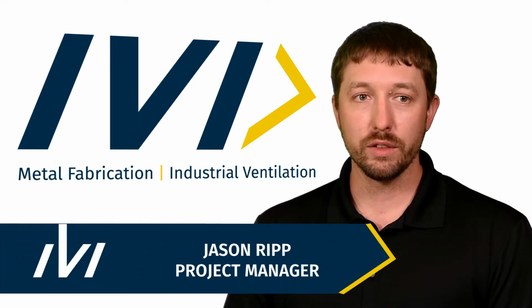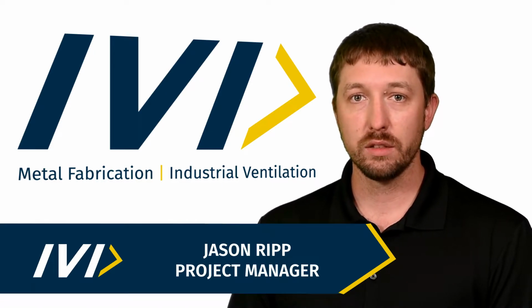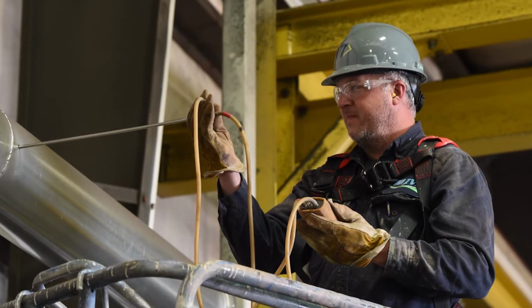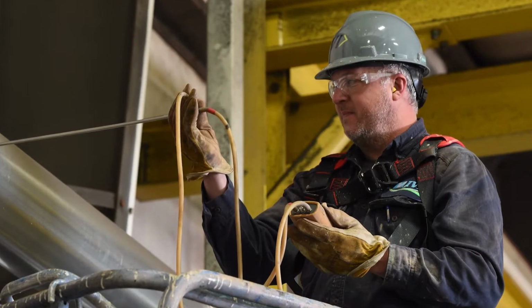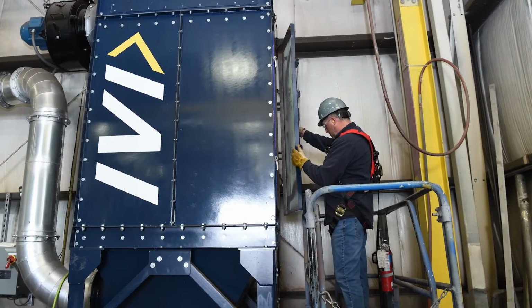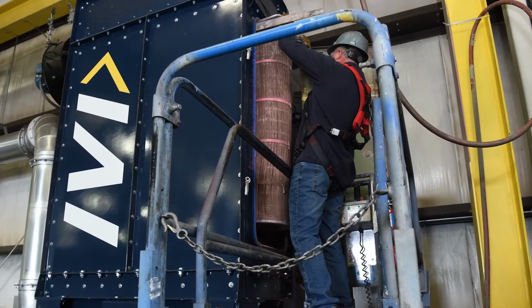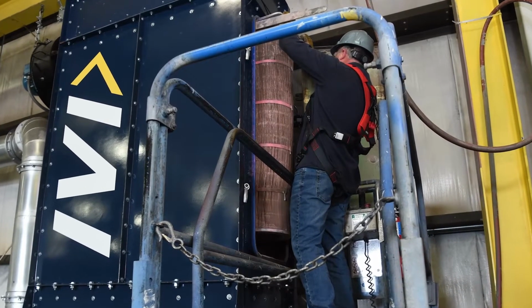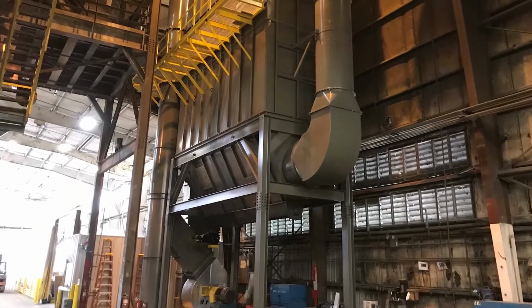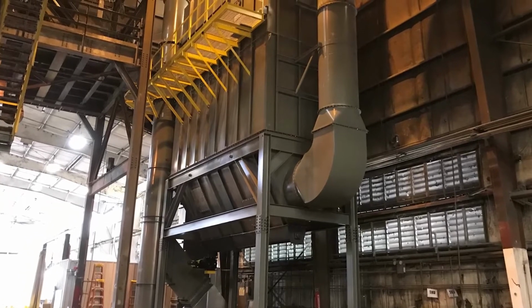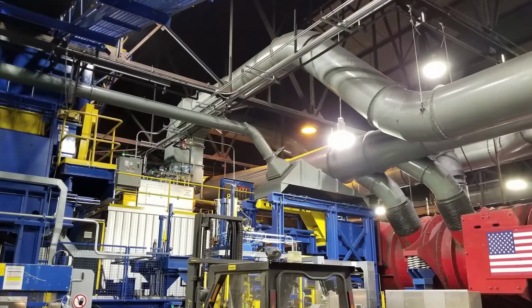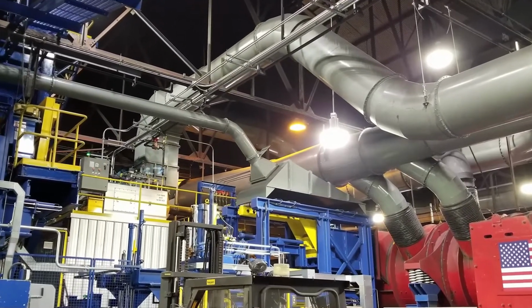What you're going to look for is where those holes are, what the sources are, what the total volume on the system is, and see if there's blinding in any of the filters. Then take it back to the collector and check to make sure all the filters are working and not leaking through the tube sheet, and then take it back even as far as the fan or the exhaust. We want to keep everything running as designed and the volumes where they need to be, otherwise it can further compromise the ductwork.